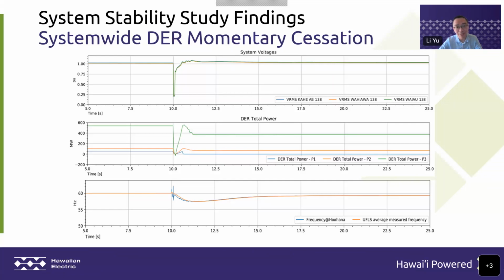However, we know that a big chunk of system load can recover along with the voltage recovery, so it does not behave like the DER recovery. So during the DER recovery, we do see a big imbalance between power and demand. That imbalance causes our frequency to start declining, as you can see in the lower plot of this slide. Because our system already has low physical inertia, and because of the missing big chunk of DER generation, frequency can decline very fast to around 57, 58 Hertz, which triggered 2 to 3 stages of underfrequency load shedding.